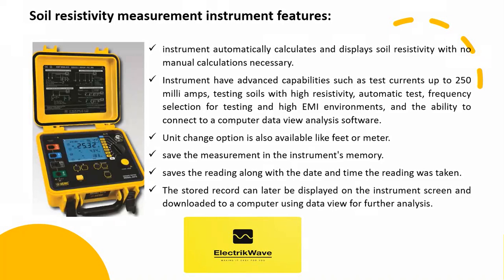Nowadays advanced measuring instruments are available, some of the features are shown here. The instrument automatically calculates and displays soil resistivity with no manual calculations necessary. Instruments have advanced capabilities such as test currents up to 250 milliamps, testing soils with high resistivity, automatic test frequency selection for testing in high EMI environments, and the ability to connect to a computer data view analysis software. Unit change options are also available, like feet or meter. You can save measurements in the instrument's memory, which saves the reading along with the date and time. The stored record can later be displayed on the instrument screen and downloaded to a computer using data view for further analysis.